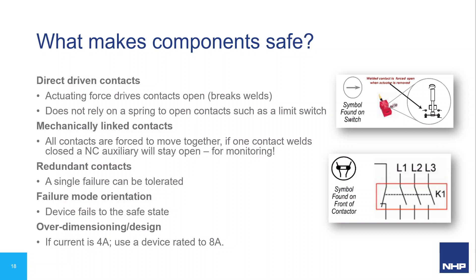Mechanically linked contacts are used in electromechanical switching devices like contactors and relays — all contacts, both main poles and auxiliaries, are solidly linked together. If any one contact is stuck in the incorrect state, all others must also be in the same state. We can use an auxiliary contact to provide reliable feedback to the safety control system. Some safety components also have multiple redundant contacts linked in parallel or series so that if one fails, the other can still perform the safety task.